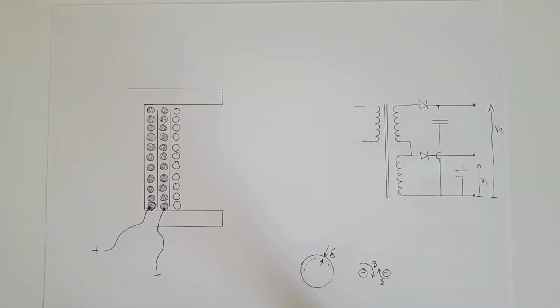Now, in the case of high voltage transformers, for example, transformers which are connected to the main supply and step down to 12 volts, it's a good idea to connect the high voltage part to a winding which is as far away from the low voltage winding as possible. And that will cut down on the interturn capacitance, and it will also cut down the chance of any flashover or breakthrough through the insulation.